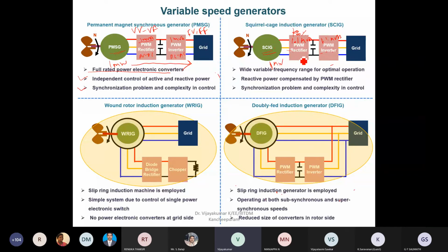Why? Because of the reactive power requirement of the machine, and also if you want to manage unity power factor at the point of common coupling, this converter can also supply the reactive power in addition to the real power. So the converter ratings are more than the machine rating in the squirrel cage induction machines, right? All the other properties are also possible here. That means real and reactive power control, synchronization, everything is possible. But here the converter ratings are more than the machine rating. So in these two topologies, we have discussed converter ratings, right?